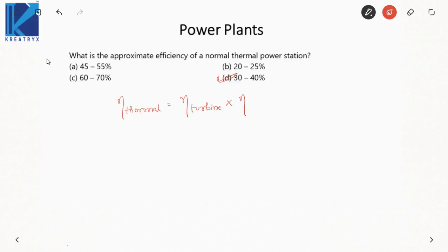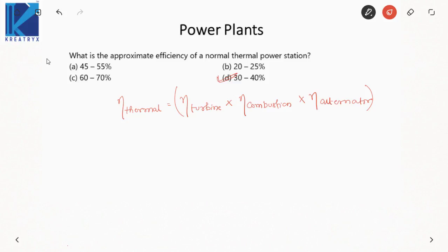The net efficiency is the product of three efficiencies. The overall process: we take a fuel and combust it, producing heat energy. That heat energy heats water, converting it to steam. The steam runs a turbine, and the turbine drives the shaft of an alternator. So, first we have eta_combustion for producing steam, then eta_turbine for the steam running the turbine, then eta_alternator for the turbine running the alternator. Net efficiency is the product of these three.